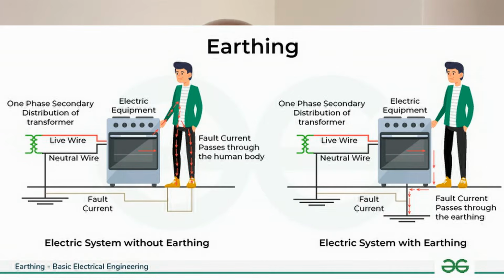What is earthing really for? Earthing is not just about passing the inspection, though that's important too. Earthing is about fault energy dissipation. Its job is to carry fault current safely into the ground, prevent dangerous touch voltages, protect people, animals, appliances, and the structure, and provide a reference point for surge protection and the lightning protection system. This is the job of earthing.